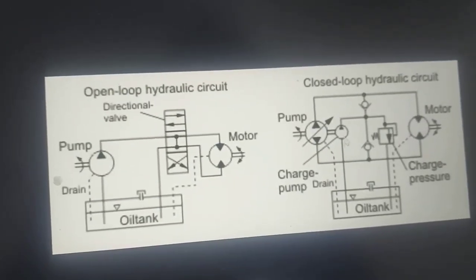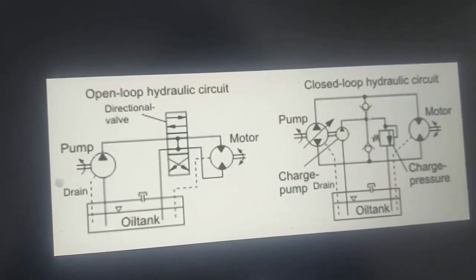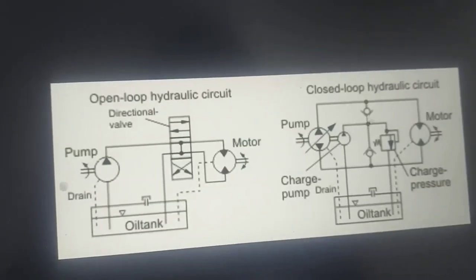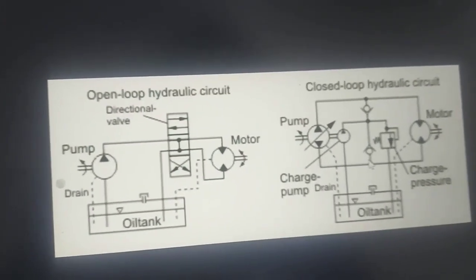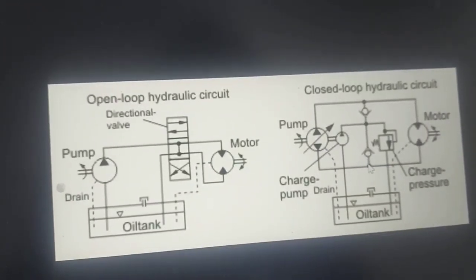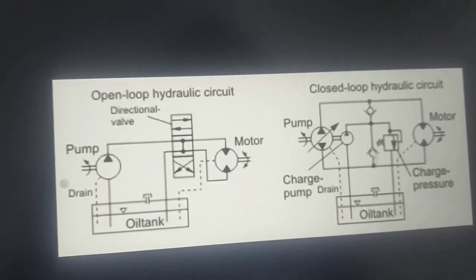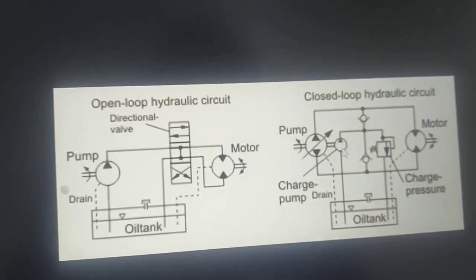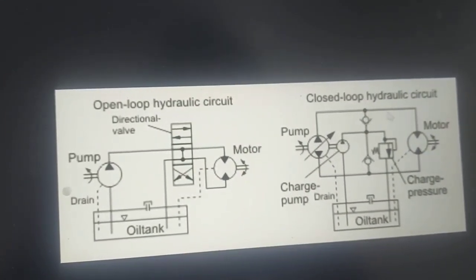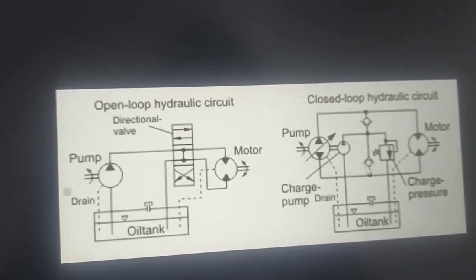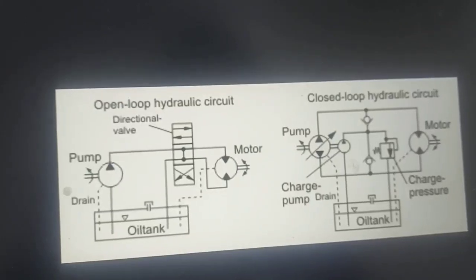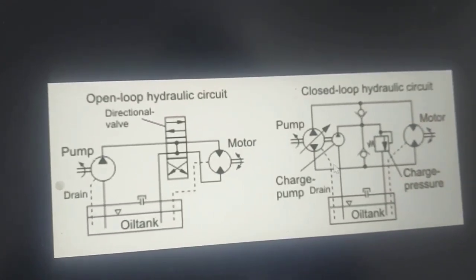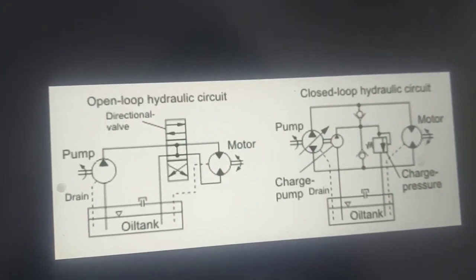From the charge pump, you can see check valves on both sides. The charge pump maintains pressure on both the pressure line and the return line. In a closed loop, if there is sometimes an air lock, the check valve opens on either side. If there is a pressure drop, the small charge pump maintains pressure on both the pressure side and return side, because the return oil goes back to the pump, completing the circuit.